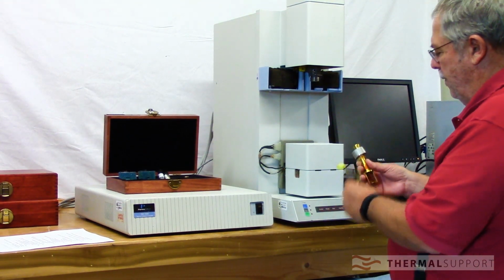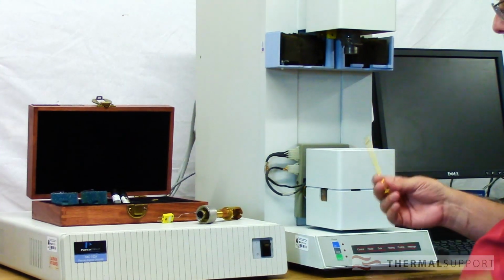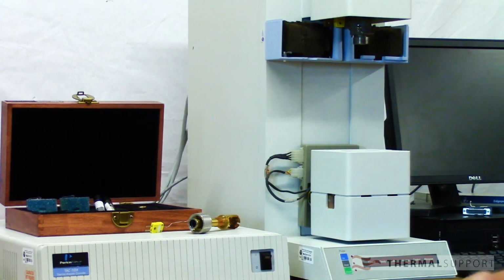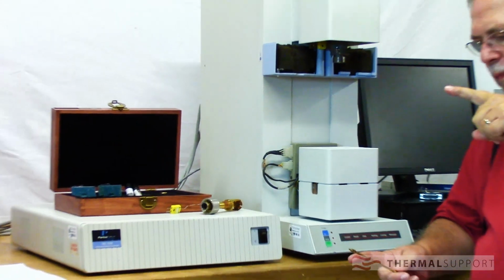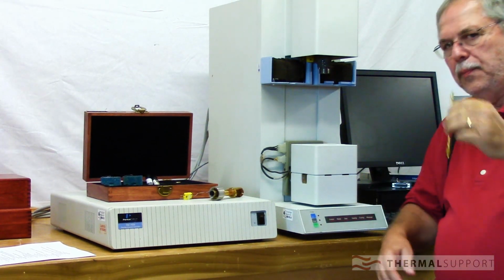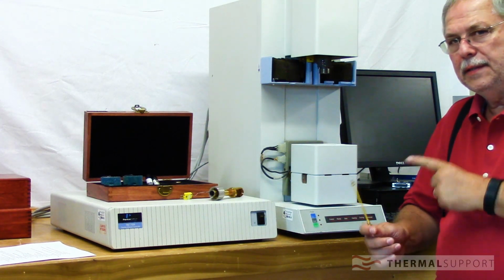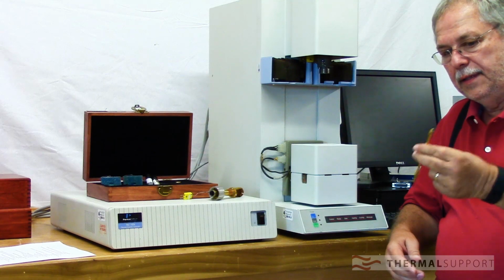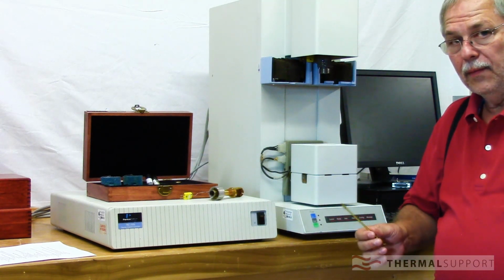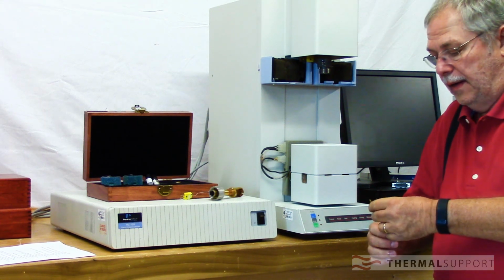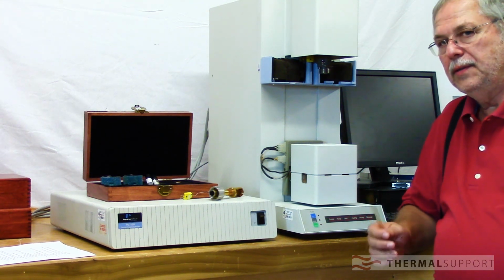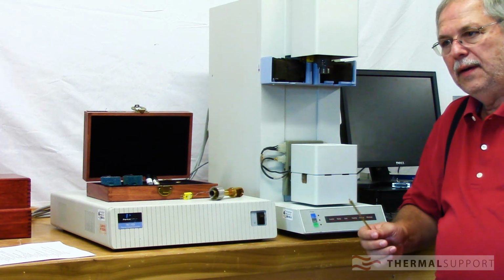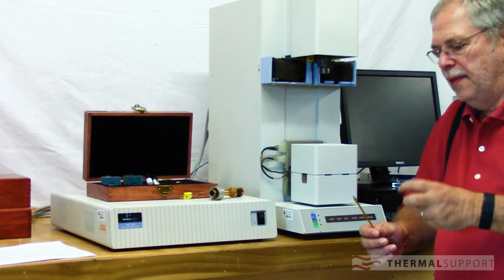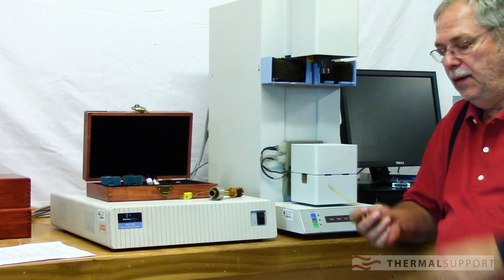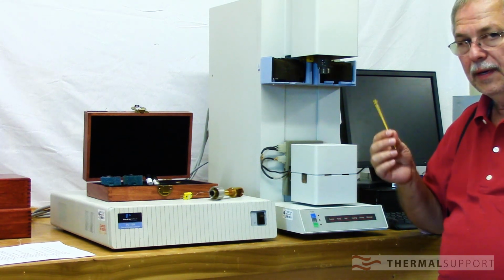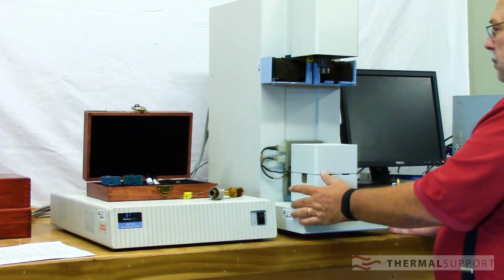We have our thermocouple here, and we're going to put our probe on. Now we have this core rod. It's about that long. As a matter of fact, I probably need to get a picture of one for the next one. It's important that it's straight. And when you put the probe on, you need to remember that core rod is stainless steel. You do not need to crank them down like a gorilla. We've had folks come in here that really turn these things tight, and you're not going to get a better connection past anything other than a real tweak. But you can physically twist the core rod, and you can physically twist this, and you're no longer straight, which can be really problematic. So our instrument's off.